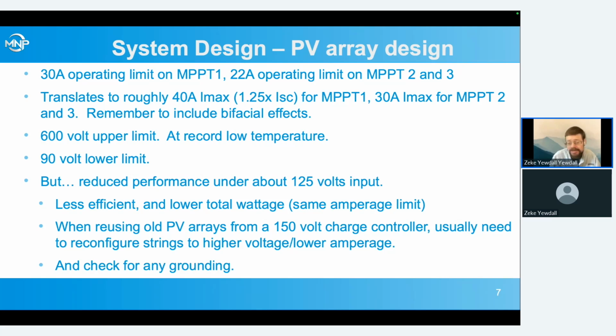Now, it doesn't matter if you're at 580, but you don't want to be above the 600. And that's just a voltage rating of all the capacitors and transistors in there. The lower limit, we've got a 90 volt lower limit, but you will see reduced performance under around 120 to 130 volts input. So while it can go lower, I would generally try not to.